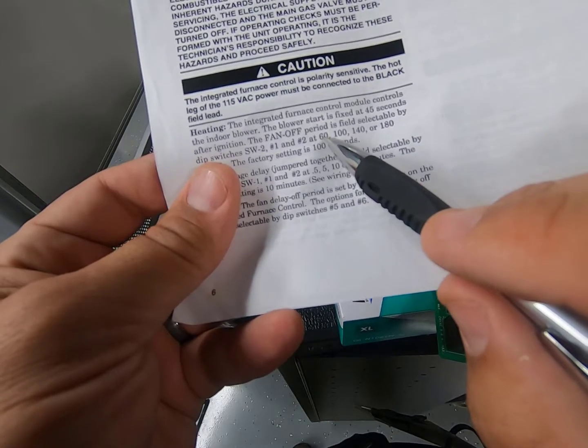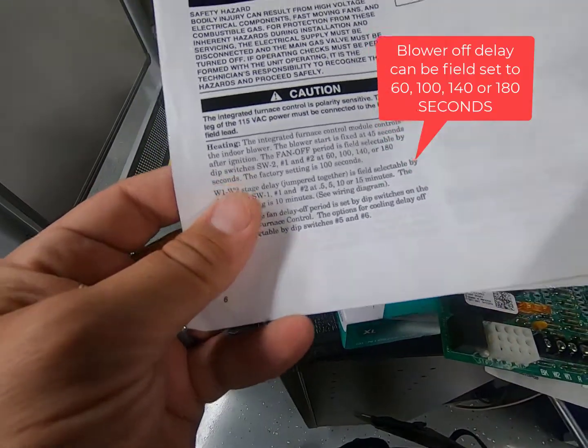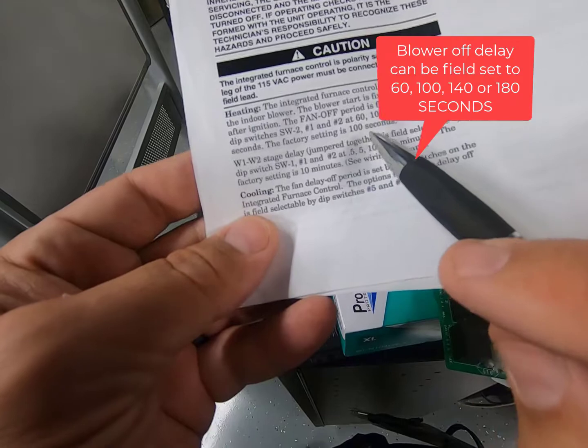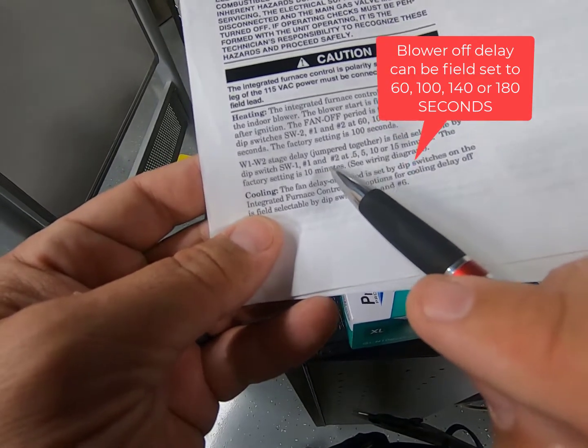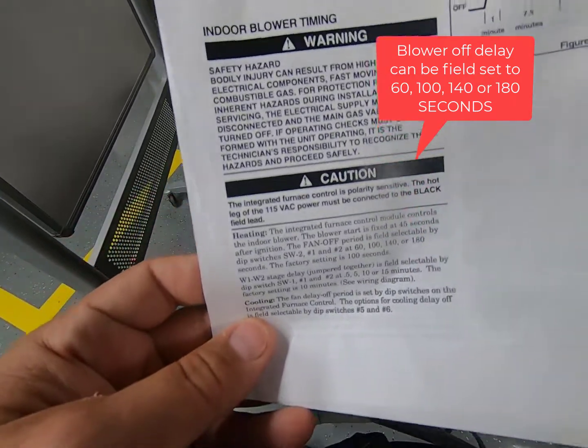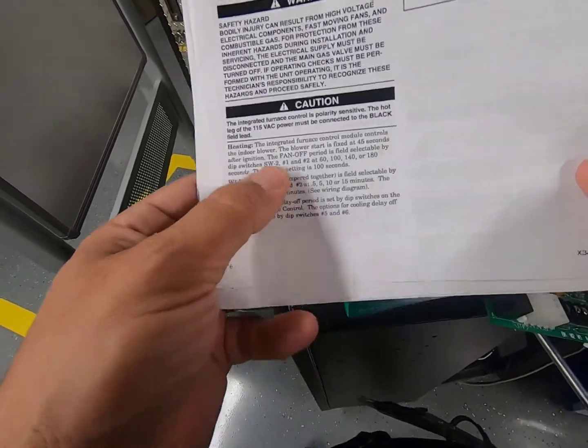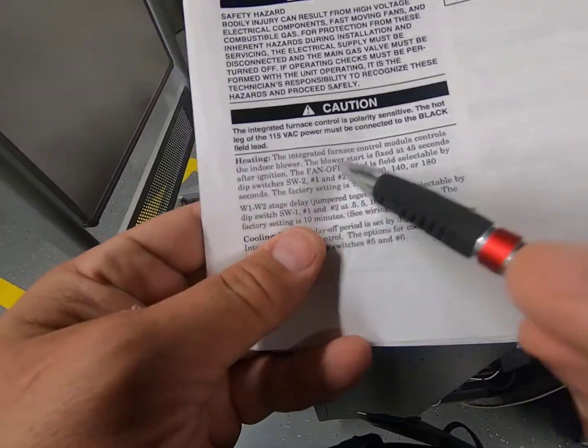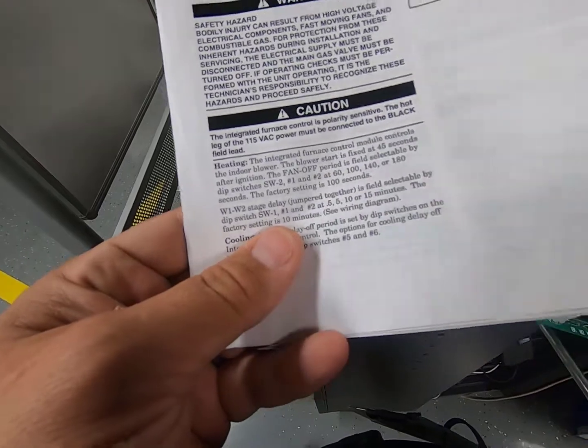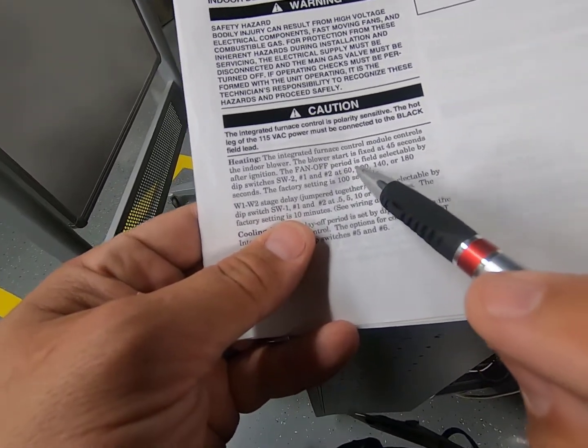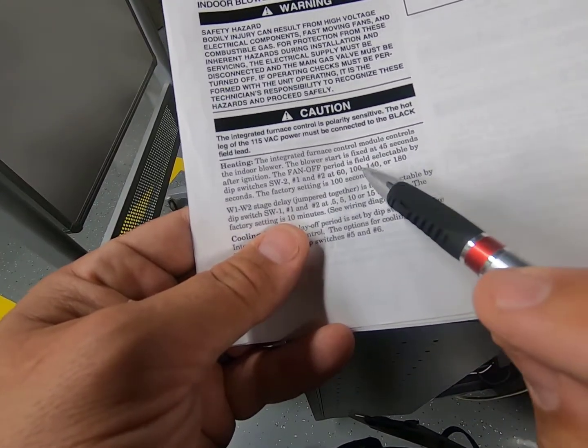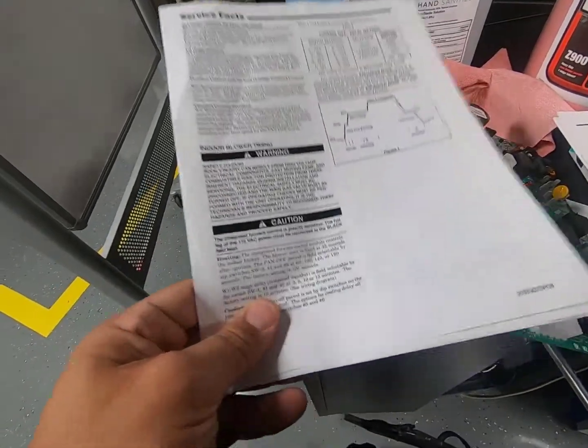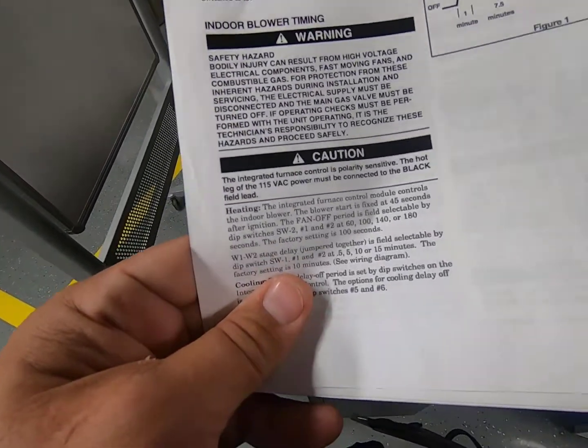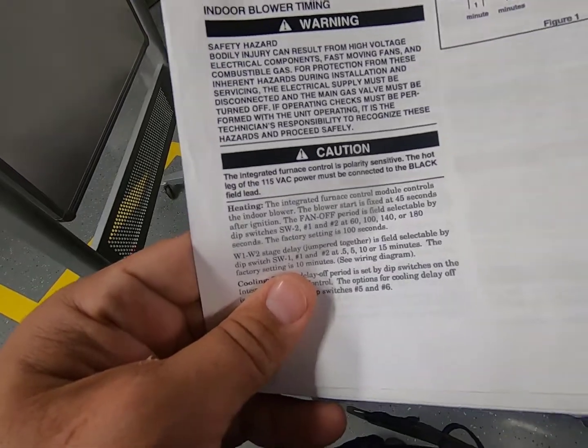So 60, 100, 140, or 180. The factory setting is 100 seconds. So what I would do is, all this is telling me is that SW2, that one block, those two switches, I can have 4 different fan off delays. So at the end of the heating cycle, how long does the big blower run before it shuts off?